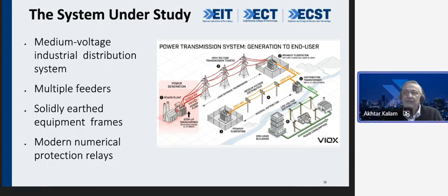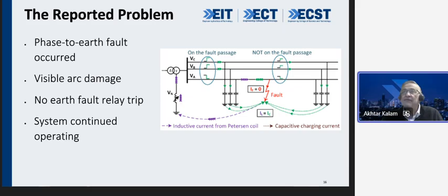So, in order to go forward with this, let us try and see what the problem is. The problem is very simple. If you look at that diagram, my friends, there's a fault over there. Can you see that red fault? It's a phase to earth fault. Look, that is A phase, that is B phase, that is C phase. So it's an A phase to earth fault.